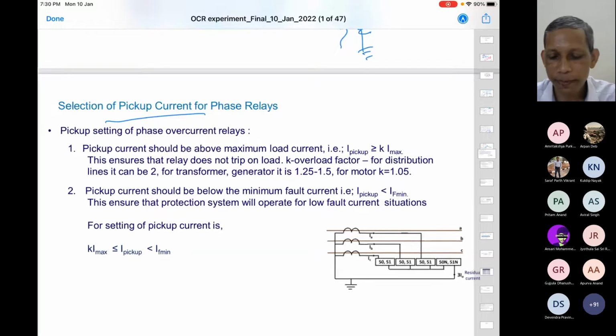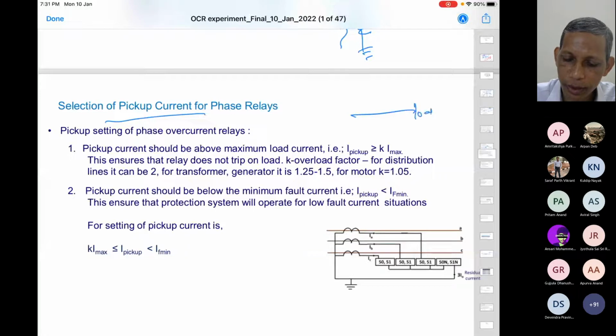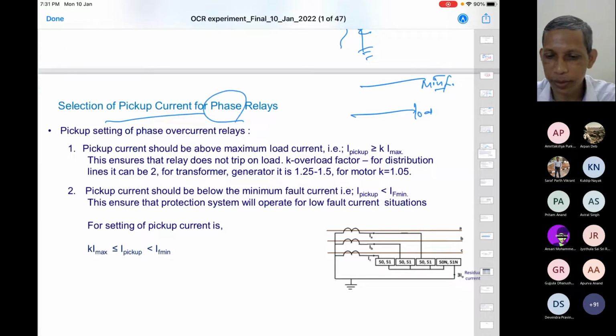For the pickup current setting, as I say, it should normally be higher than the load current level, and it should be around or below the minimum fault current level. That should be the guideline. A phase relay, as you know, is not involved with ground. What should be the corresponding selection process? Similarly, we will come to the ground perspective. The pickup current should be K times Imax, where Imax is the maximum load current. K is a factor.